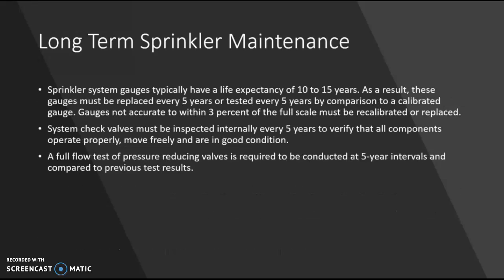The gauges usually have a life expectancy of 10 to 15 years. This is a big thing. You go into a system and you find an incorrect gauge. It can tell you the complete incorrect information for your system. And we need to make sure that those things are actually calibrated and actually work correctly to where the full scale of the whole system gets calibrated correctly and works to save lives naturally.